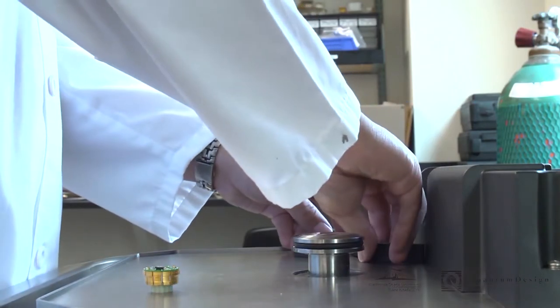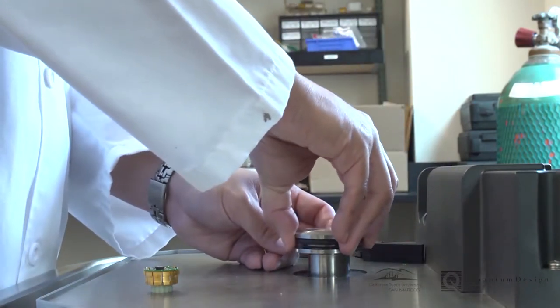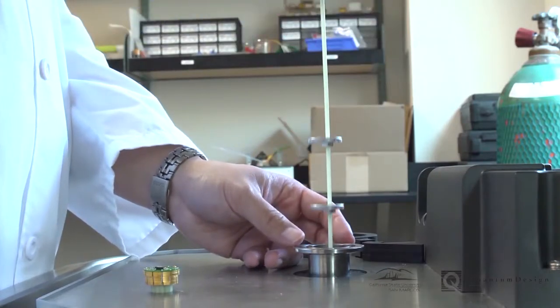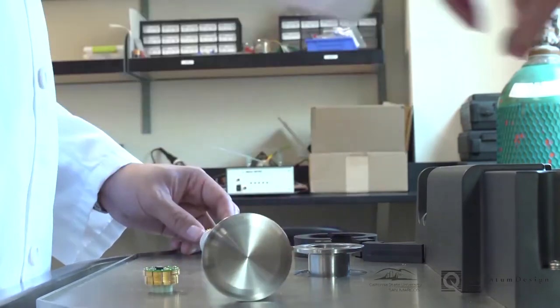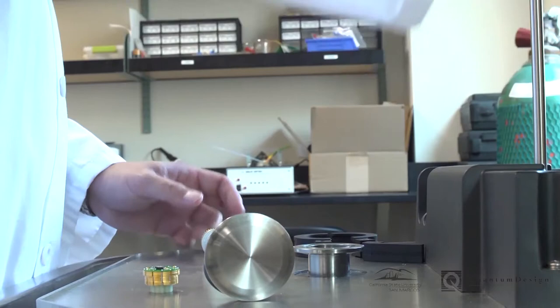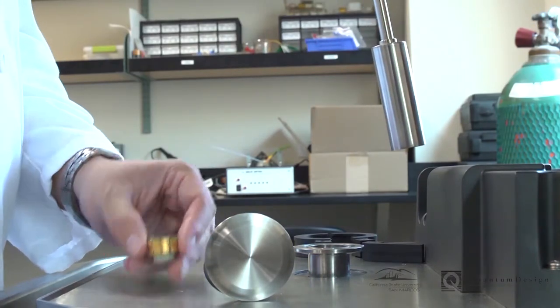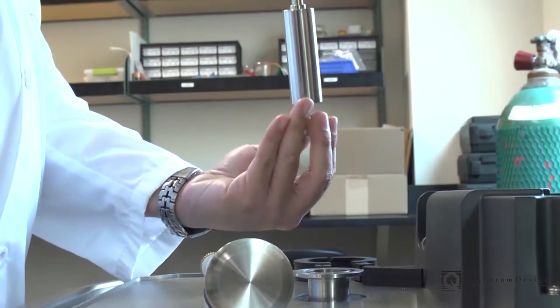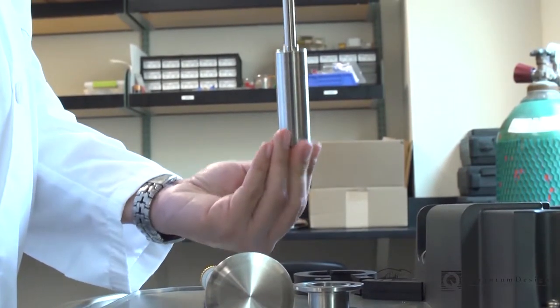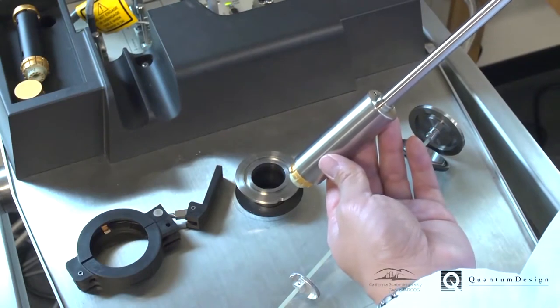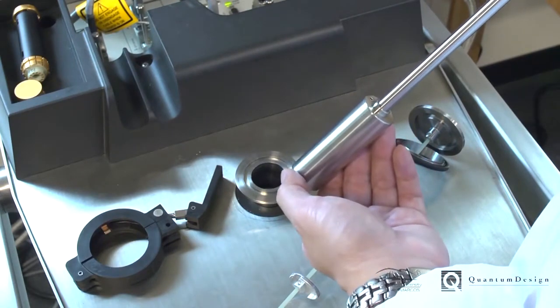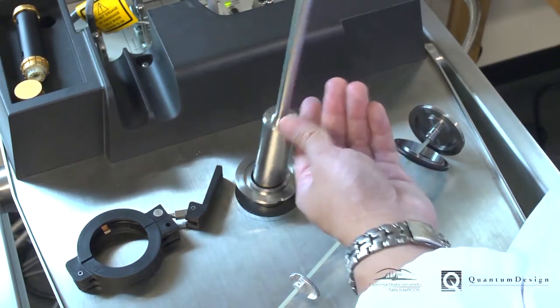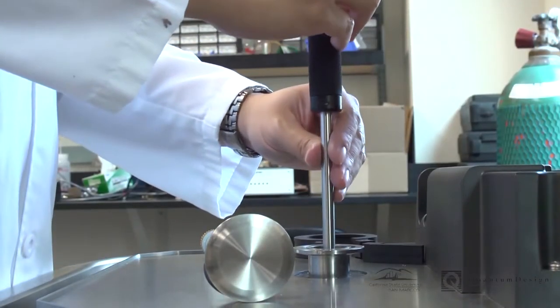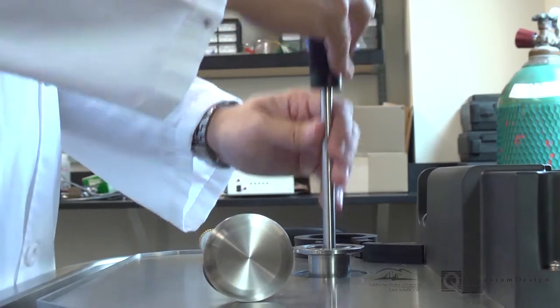Once you are satisfied with your puck contacts, it's time to load the sample into the instrument. Remove the baffle, and lock the puck into the puck insertion tool. Make sure it's snug. The notch is important, as the VersaLab is keyed such that the puck notch faces you. We recommend inserting the puck with the notch pointing 90 degrees away from you, and then rotate the tool. When you feel the puck slip into place, give it a nudge downwards and unlock the tool. Remove the insertion tool and close the baffle.